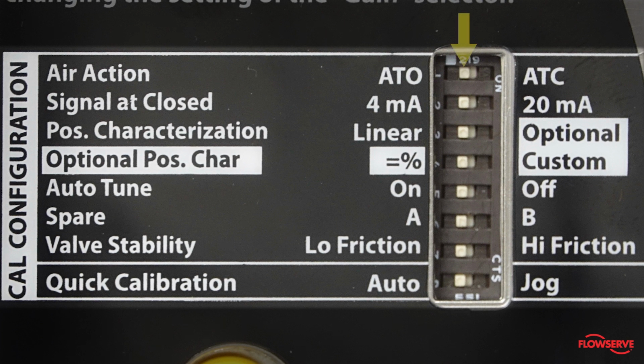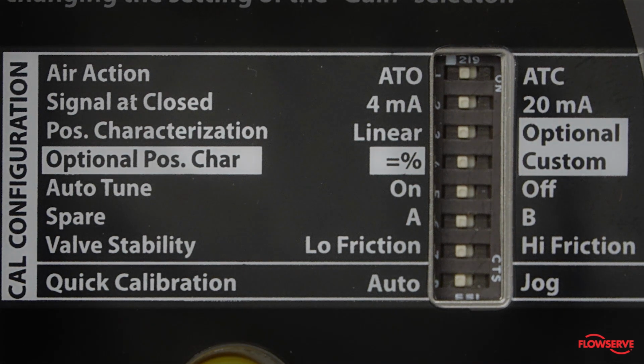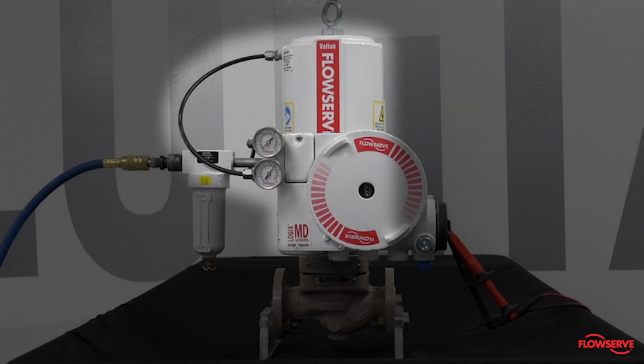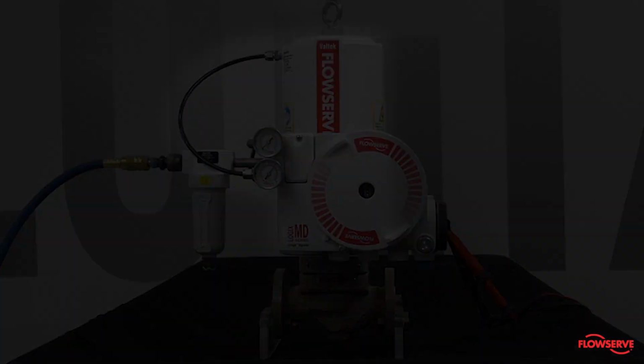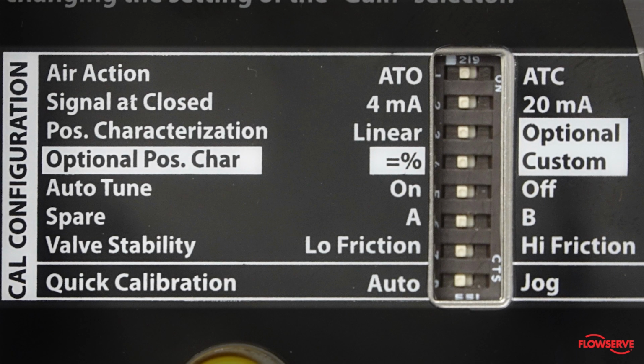For example, changing the air action dip switch does not change whether the valve is air to open or air to close. To change this, the physical configuration of the valve spring and tubing must be changed. Keeping this in mind, the first dip switch is called air action, which will tell the positioner whether your valve is air to open or air to close. For this example, the valve is set air to open with the white dip switch set to the left.